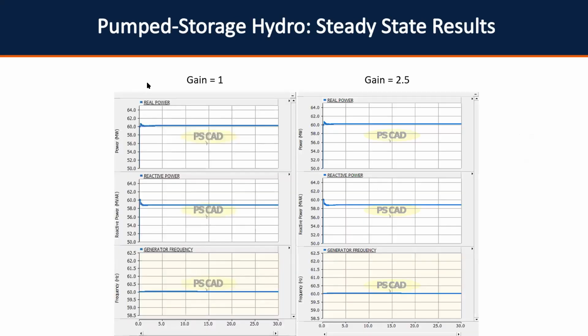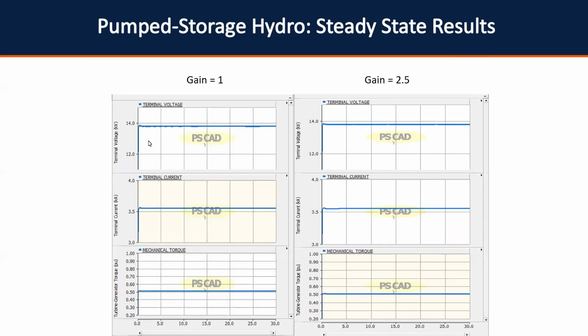So here are the steady state results. The left side is water, with a gain of 1, and the right is the gain of 2.5. I've got 2 slides for this. Everything looks pretty much identical across the board. Here you do see a little bit of a difference, on the next slide down with terminal voltage, current, and torque. I should have made this bigger, but down here in mechanical torque and terminal current, you see a little bit of a dip where it's not on the other side, and a little bump here. I think that's because of the difference between the initial operating head and the torque input to the generator, but definitely not enough to throw it into any kind of instability range. Otherwise, they're pretty much trending the same way.